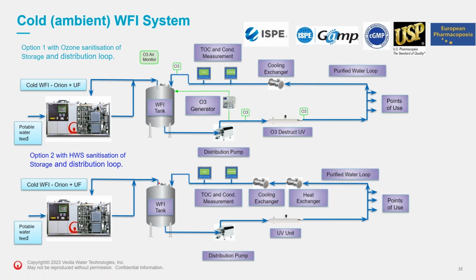Some companies we've talked to are also looking at hot water sterilization on this type of system, where you take the temperature up to 121 degrees, with the water under pressure at 1 bar. So some companies are looking for that as well, just as a belt and braces type system. And the frequency of these, again, will depend on your QC and your sampling regimes, and your trends will dictate how often you would sanitize these systems.